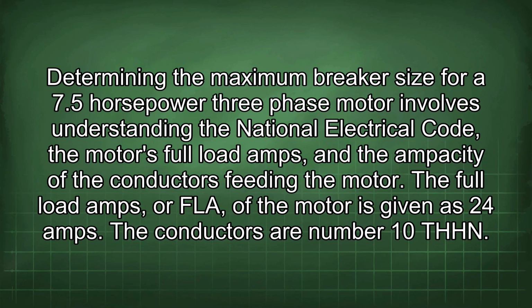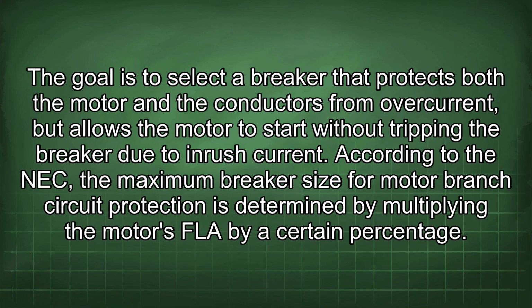Determining the maximum breaker size for a 7.5 horsepower three-phase motor involves understanding the National Electrical Code, the motor's full load amps, and the ampacity of the conductors feeding the motor. The full load amps, or FLA, of the motor is given as 24 amps. The conductors are number 10 THHN. The goal is to select a breaker that protects both the motor and the conductors from overcurrent, but allows the motor to start without tripping the breaker due to inrush current.